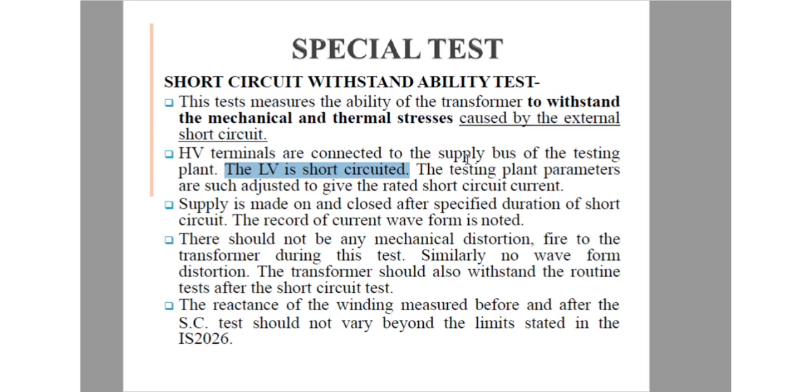Similarly, there should be no waveform distortion, and the transformer should also withstand the routine tests after the short circuit test. The reactance of the winding measured before and after the short circuit test should not vary beyond the limits stated in IS 2026. So we have to see this IS and follow it for the short circuit withstand ability test.